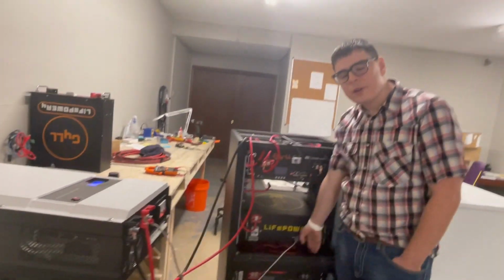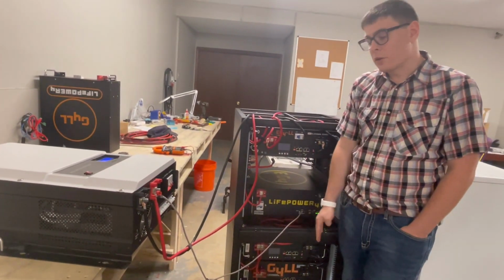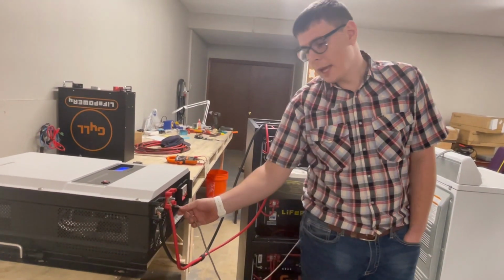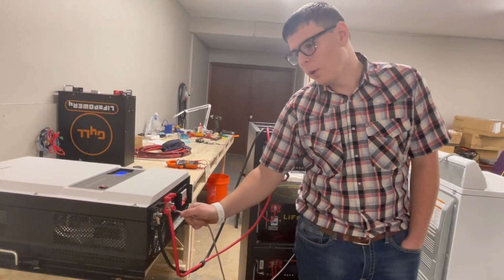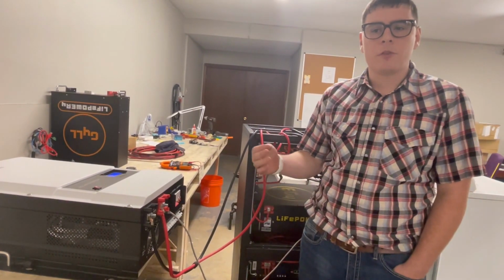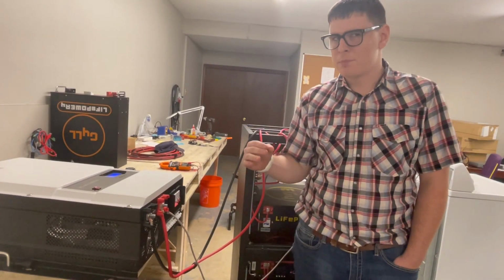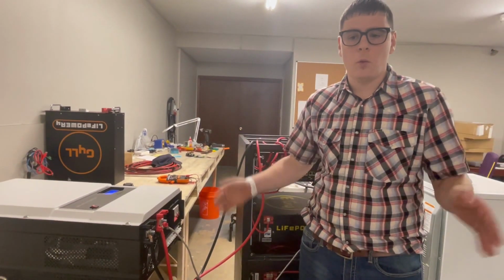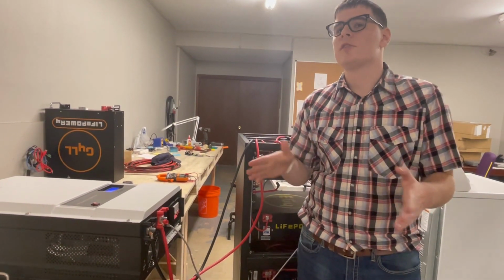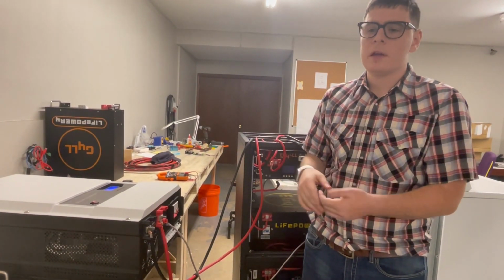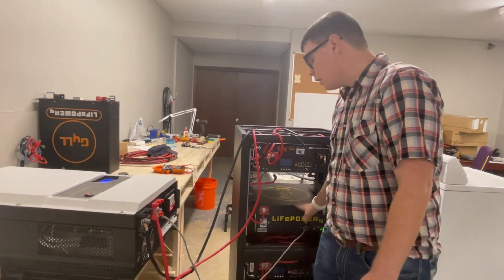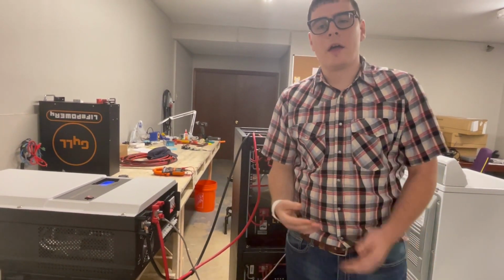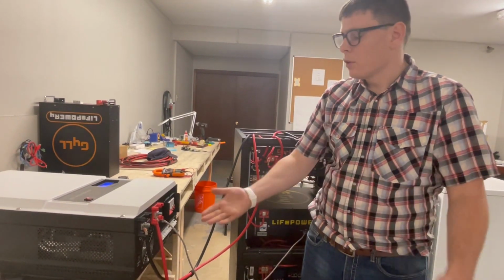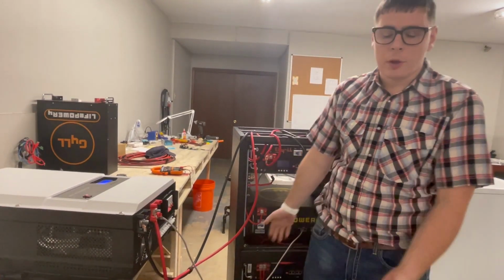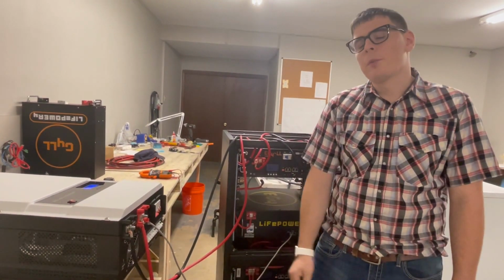So that's really it. To recap, make sure your master battery is set to address zero. If you're going into a 12 kilowatt, make sure you're communicating with the BMS port on the 12 kilowatt. If you're going into a 5 kilowatt, make sure you're communicating with the RS-485 port. If you have multiple 5 kilowatts, make sure you get a hub to communicate each inverter into the hub, and then communicate the battery into that hub as well, so that way you can distribute the communication cables coming from the batteries. And that's really how simple that it is.